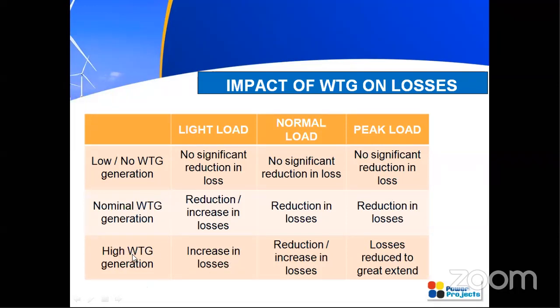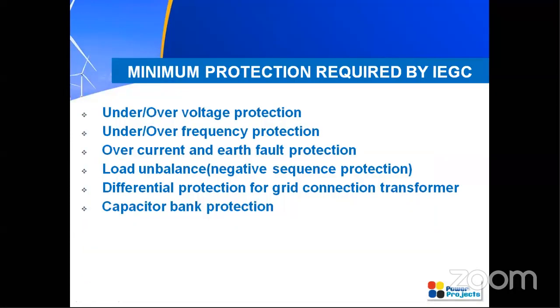But this is the important case to be considered. When you go for high generation and you have a light load, your losses will be greatly increased. Whereas in the case of normal and peak load, it will be reduced. So when the wind generation is high and the load is light, it will increase the losses. This is also one impact, and you have to check it.